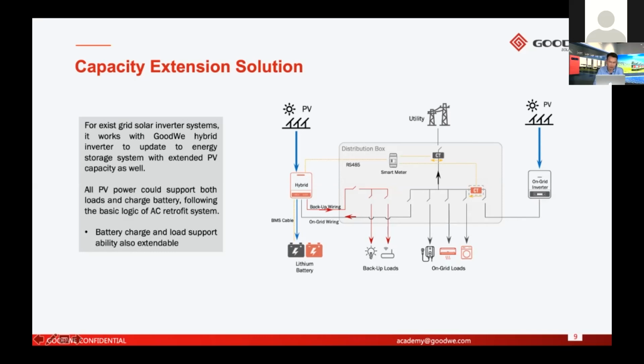Okay, so what are the advantages of this solution? Like we talked, for pure AC coupled inverters working with on-grid systems, if the grid fails, the PV cannot work. So only the battery and the backup are working if the grid fails for pure AC coupled inverters. But if you use a hybrid inverter with on-grid systems, if the grid fails, this PV system cannot work, but the solar connected to the hybrid inverter can still work. So this is the big advantage of a hybrid inverter working with on-grid systems. And for all our hybrid inverters, no matter whether single phase or three phase, it can work this way.